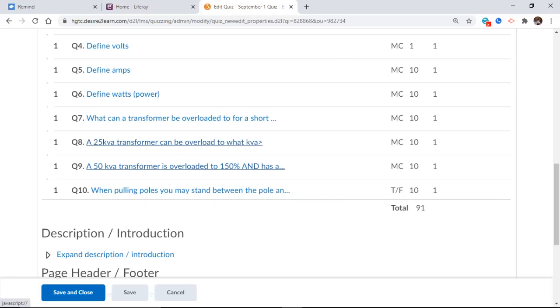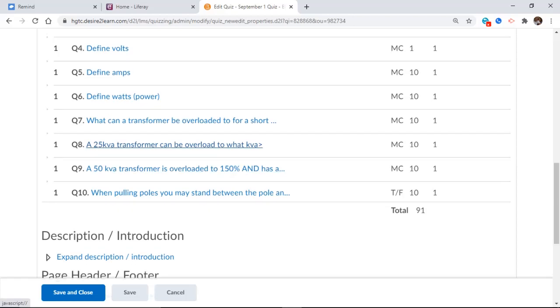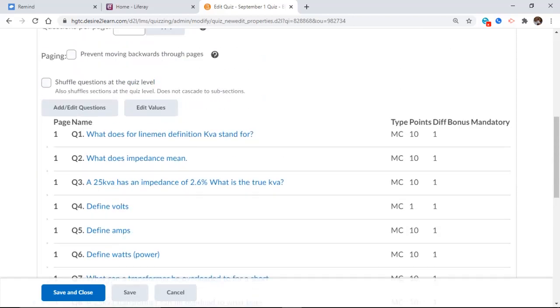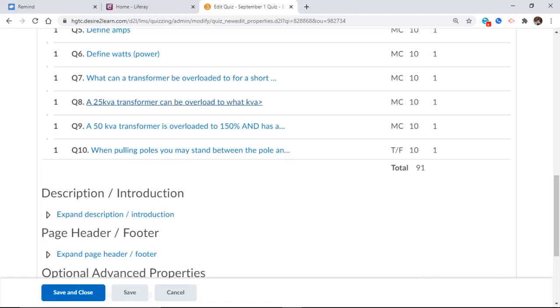A 50 kVA transformer is overloaded to 150% and has an impedance, I know what that is over there. So you're going to have to overload it to 150% and then calculate the impedance to give me the final kVA. So what I'm doing right here is an impedance and an overload all in one question.